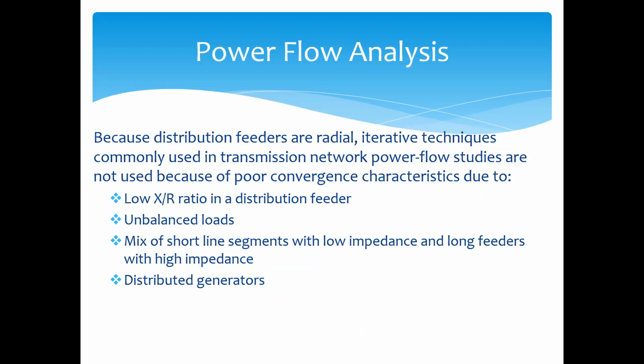Because the distribution feeders are radial, the iterative techniques used for transmission network power flow studies are not used because of poor convergence. Why are they not converging? Because distribution feeders have a low X to R (reactance to resistance) ratio, and they have unbalanced load. Further, there is a mix of short line segments with low impedance and long feeders with high impedance. And due to distributed generators, for these reasons we cannot use the load flow tools which we use in transmission studies.